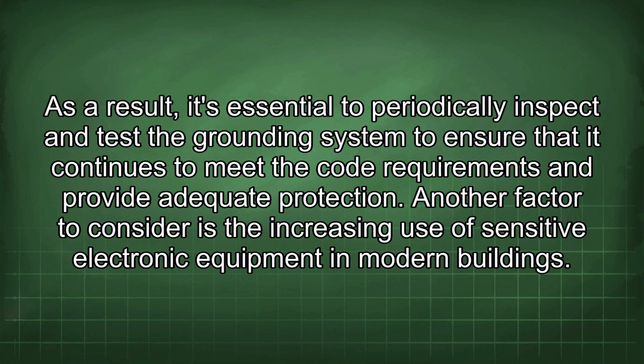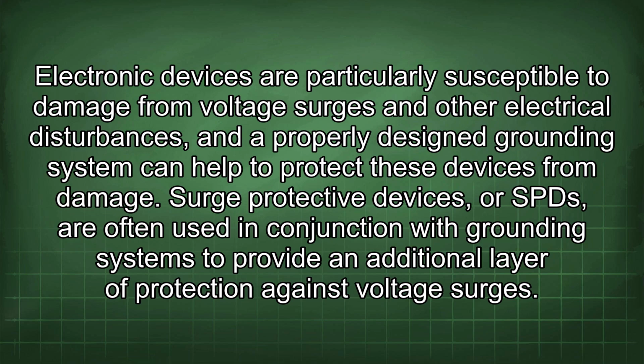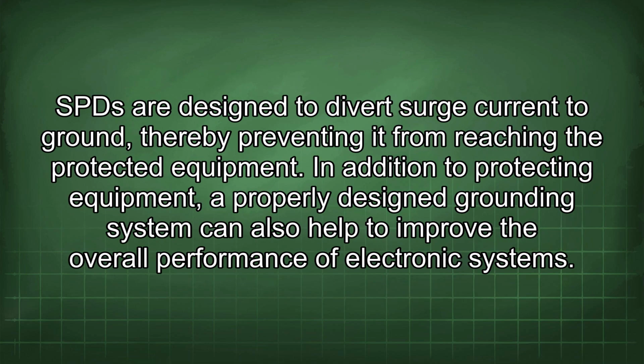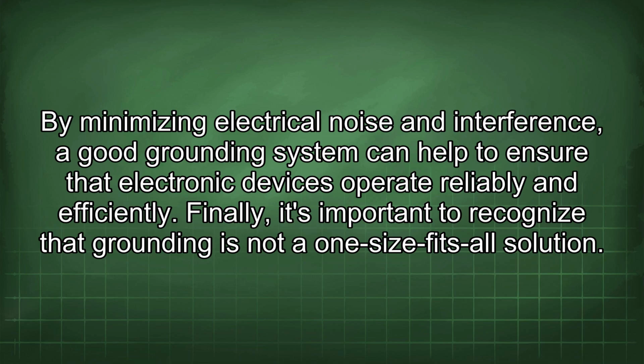Another factor to consider is the increasing use of sensitive electronic equipment in modern buildings. Electronic devices are particularly susceptible to damage from voltage surges and other electrical disturbances, and a properly designed grounding system can help to protect these devices from damage. Surge protective devices, or SPDs, are often used in conjunction with grounding systems to provide an additional layer of protection against voltage surges. SPDs are designed to divert surge current to ground, thereby preventing it from reaching the protected equipment. In addition to protecting equipment, a properly designed grounding system can also help to improve the overall performance of electronic systems. By minimizing electrical noise and interference, a good grounding system can help to ensure that electronic devices operate reliably and efficiently.